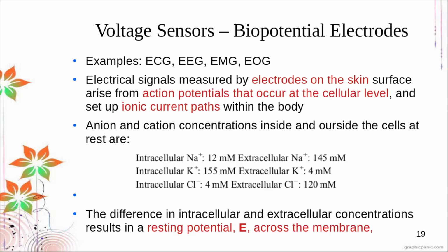You might see this especially for ECG. ECG devices are usually placed on the chest area and then the arms and the legs. Now, although when we touch them we don't really feel any electric currents, that's because the electrical currents in our body are too small to be detected by us. That's the thing with voltage sensors for biomedical devices: they must be sensitive enough to actually sense the ionic currents in the body.